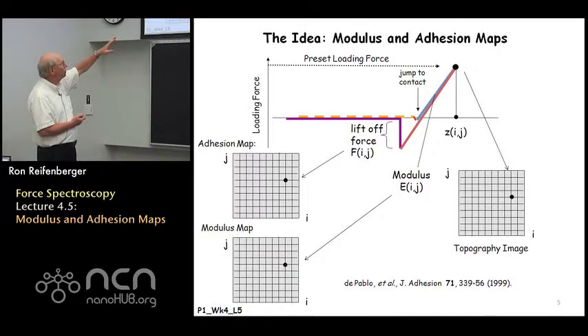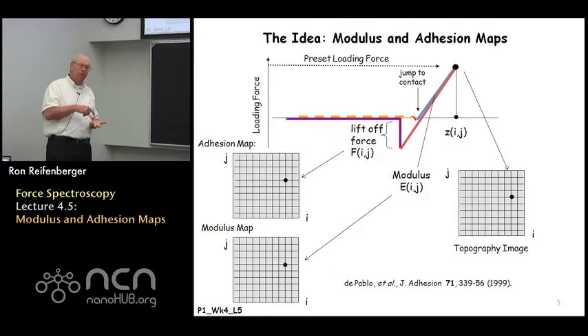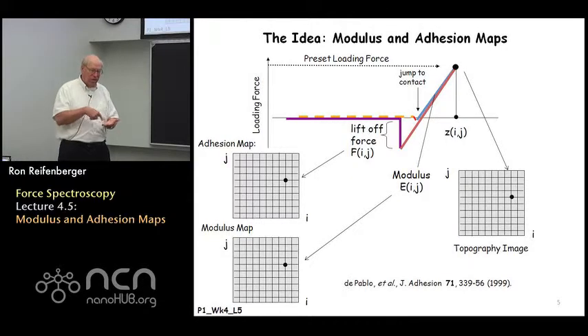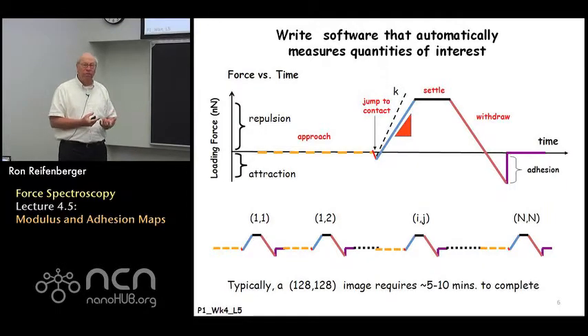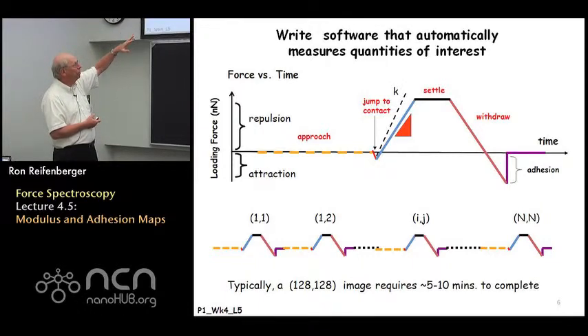Simultaneously, there's no reason you couldn't measure the slope of the force versus displacement curve — that slope is related to the modulus of the sample at that particular point. So you could imagine making a modulus map simultaneously with the topographic map. And by measuring the lift-off force when the tip is at a particular point on the substrate, you could also make an adhesion map as the sample is scanned. All you have to do is write software flexible enough to pull relevant information off the force versus displacement curve — plotted as a function of time — in a periodic and systematic fashion.